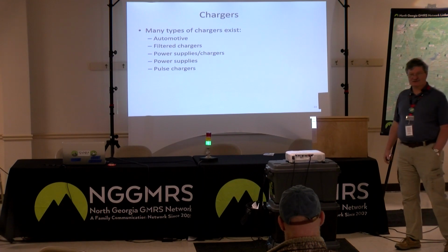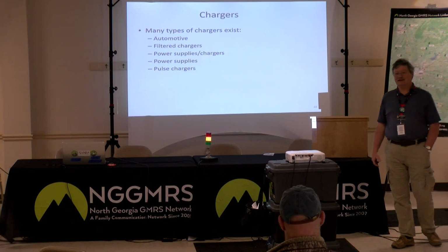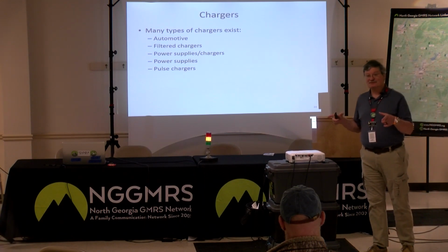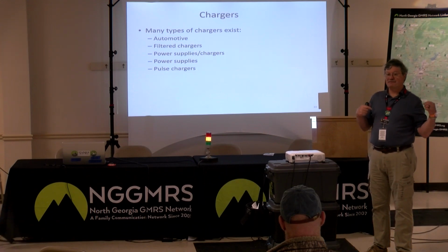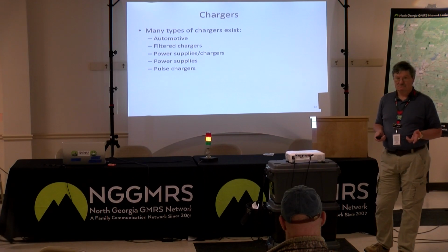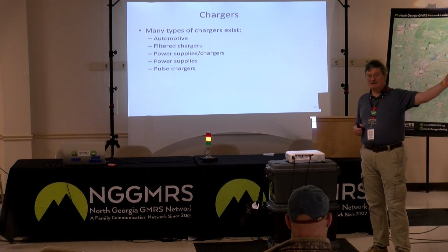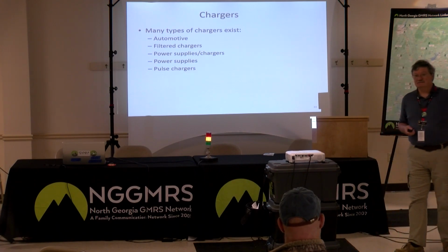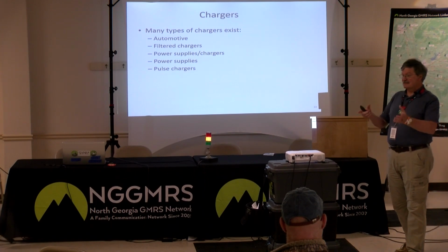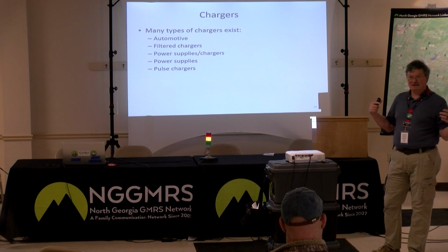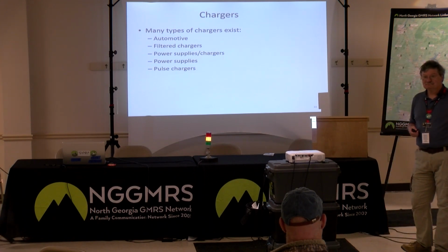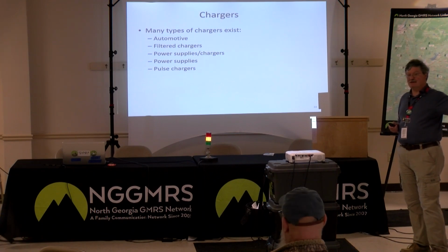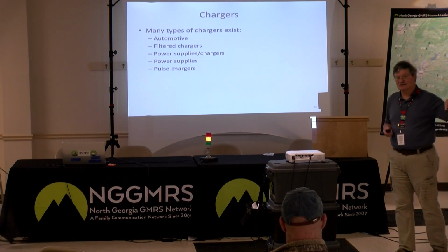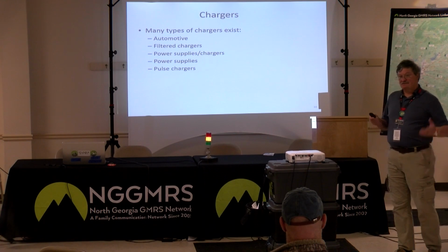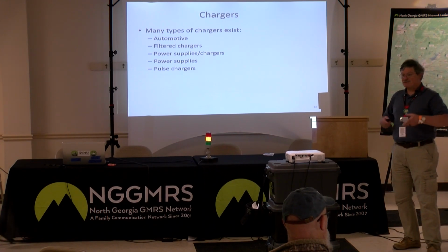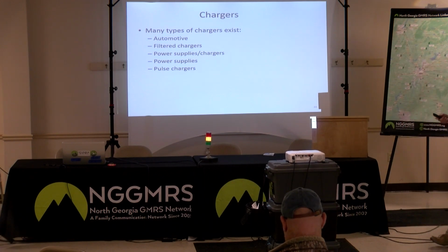Power supply / battery chargers - now we're getting into units where I can use that battery while it's on the charger, but that power supply charger can also run other equipment at the same time. This is what utilities do. Because this substation needs to trip a breaker, the battery provides the energy for tripping that breaker. Meanwhile, the power supply is keeping the battery fully charged and running all the other little instruments until that breaker needed to trip. For a few seconds they get power from the battery because the breaker takes more energy than the charger provides, then the breaker's tripped, everything gets back to normal, and it recharges the battery and keeps all the other loads happy. That's what they do.